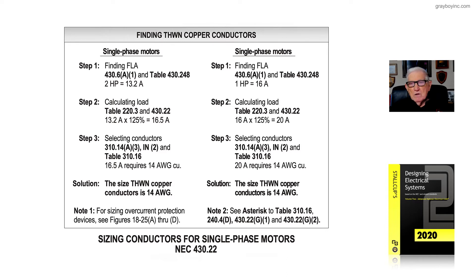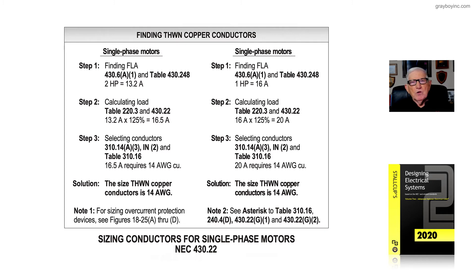Step two: go to Table 220.3. That table references certain sections based upon the type of equipment or load you're dealing with, giving you the percentage used to determine the full-load amps for any particular piece of equipment. Notice it's 125%.